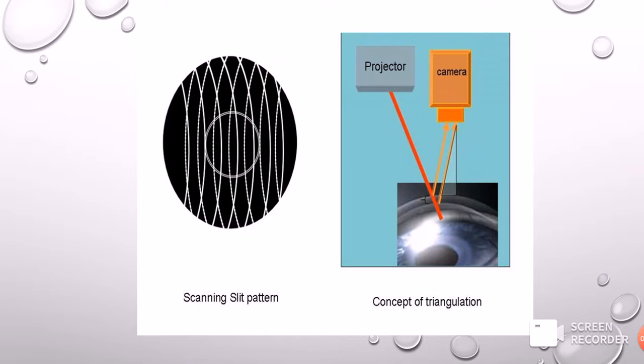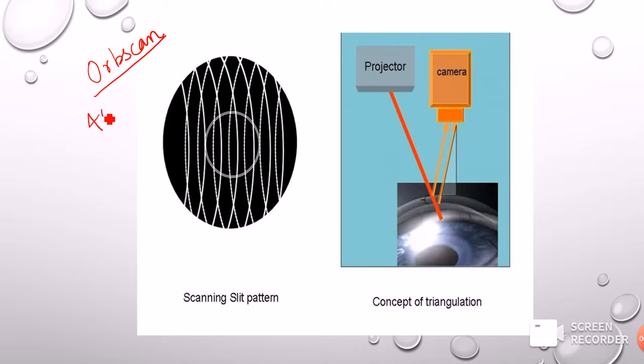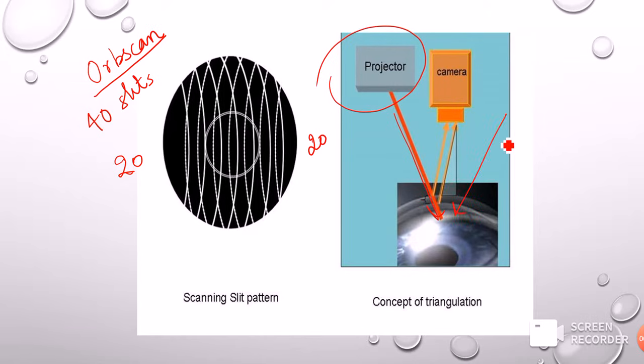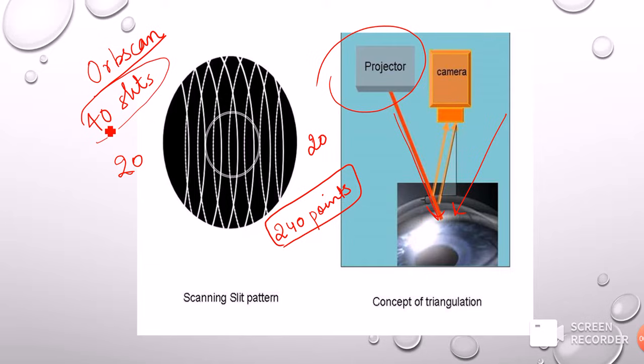Because of the disadvantages of Placido disc — measuring only the anterior curvature — we have the next technology: scanning slit, also called scanning slit elevation technology. Multiple complementary slits are used to assess the corneal surface. The example is the Orbscan, where about 40 slits are projected — 20 from the nasal side and 20 from the temporal side. On each slit, about 240 points are evaluated, giving a total extensive study of the anterior curvature, posterior curvature, and pachymetry — the thickness of the cornea.